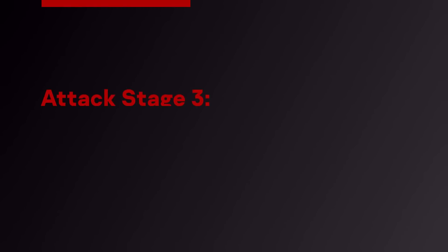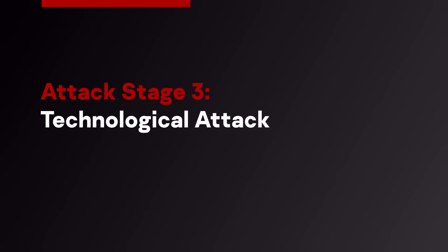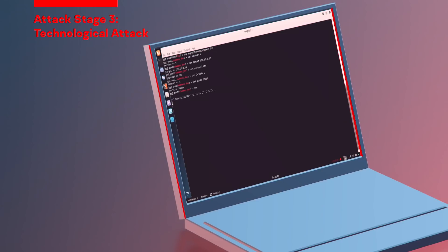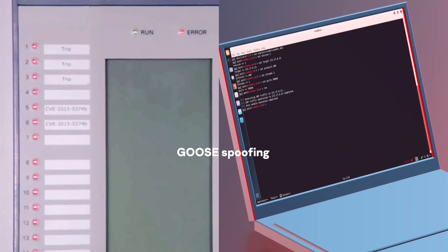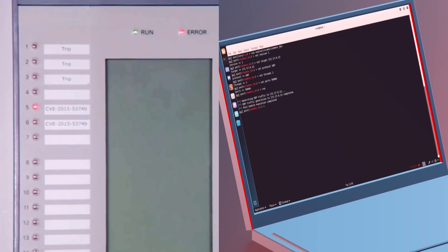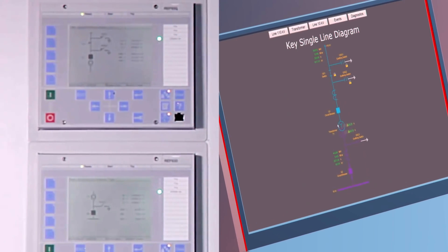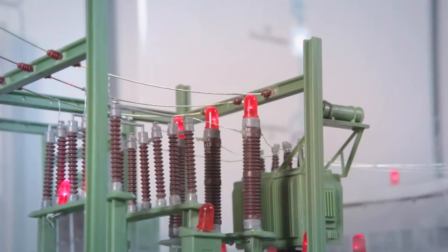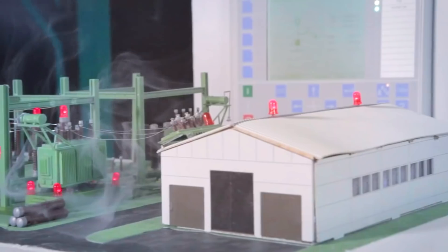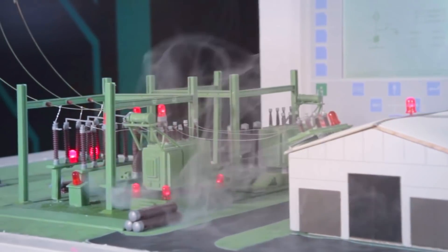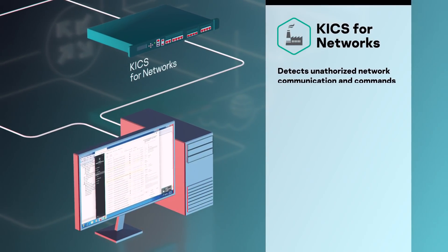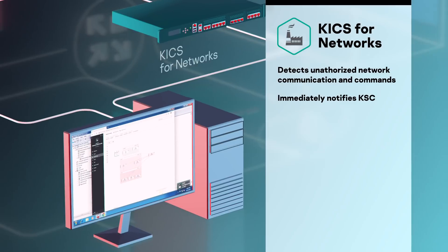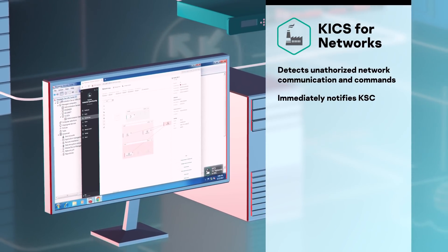If the threat is not stopped at the second stage, the attackers proceed to the third stage and attack on the technological process. The attacker exploits a known vulnerability in the firmware by sending an inappropriate update command that causes the device to stop fulfilling its protection functions. This allows the attacker to bypass the interlock of the earth switch on the energized line. The attacker can then cause a short circuit by earthing the line near the transformer. Since the protection relay was made inoperable, the circuit breaker is not tripped and the short circuit current affects the equipment, which is likely to result in the transformer catching fire or damage to nearby equipment. KICS for Networks detects all unauthorized network communications and anomaly commands and immediately notifies Kaspersky Security Center, where we can see malicious communications that make relay protection fail.